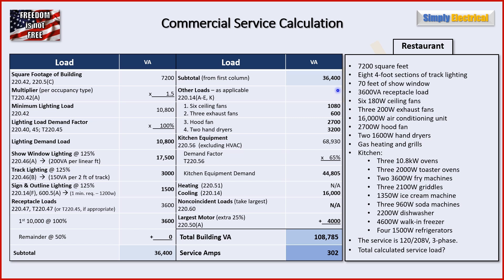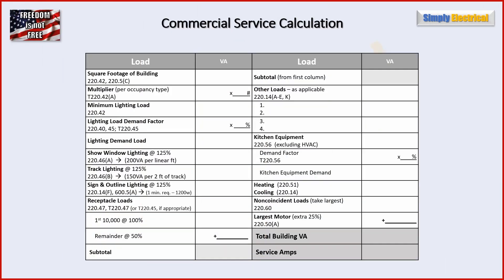Once we have all those numbers, we add all the bold numbers together and come up with 108,785 VA for the building total. Then we divide by our voltage — 208 volts, multiplied by the square root of three because it's three-phase — and we come up with 302 amps. Now we can size our feeders, conduit, service, and overcurrent protection devices. And it's really as simple as that. I've also shown a blank version of the table so you can screenshot it, make copies, use it as a worksheet, print it out, and use it on the job site.